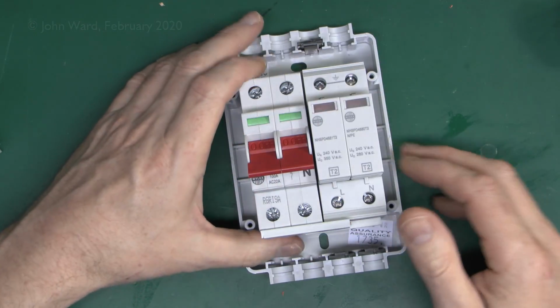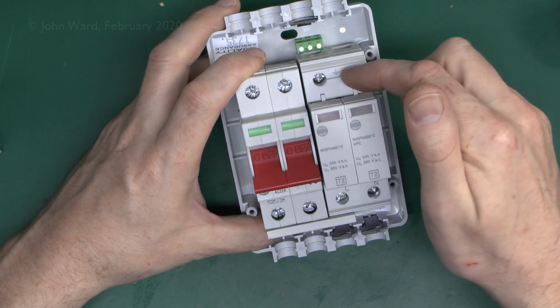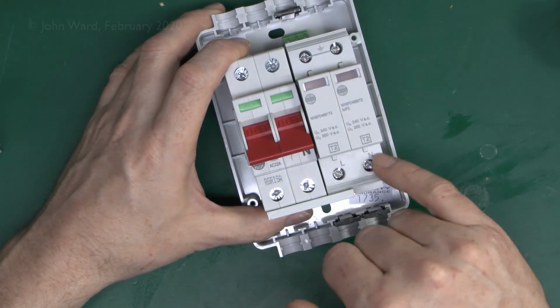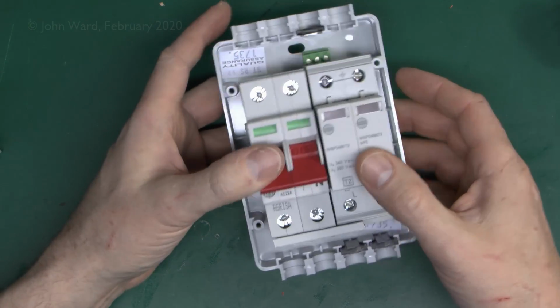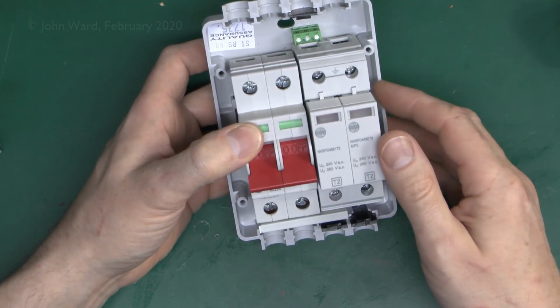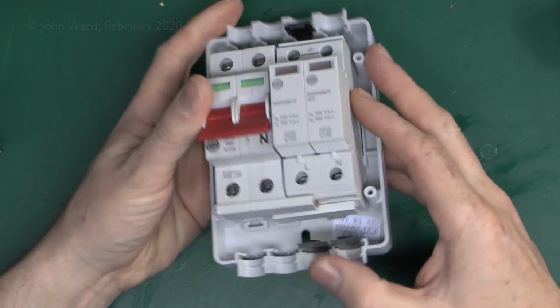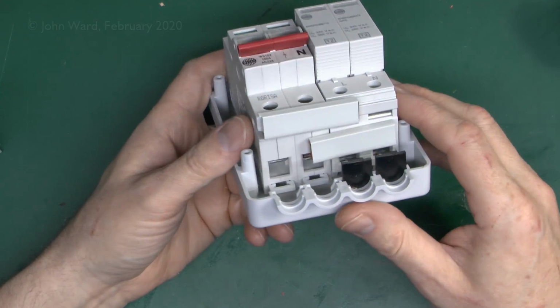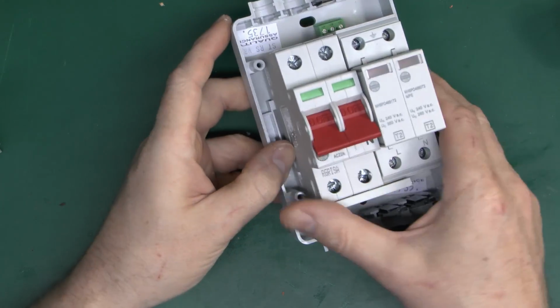But in terms of the wiring, it's pretty much exactly the same. Earth connection here, it's got 2 terminals for that, and line and neutral. Now so this is a standalone item, and it's intended to be placed as your main isolator with the surge protection in it, and the connections here just go across the bottom. That's actually how it's supplied from the factory.